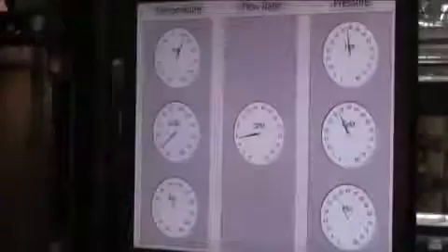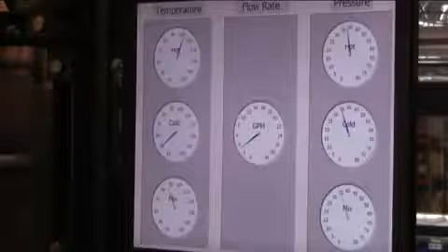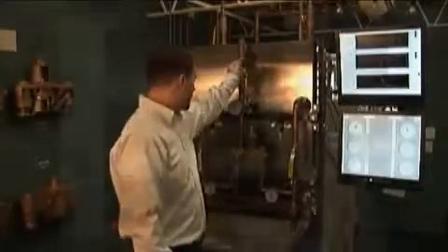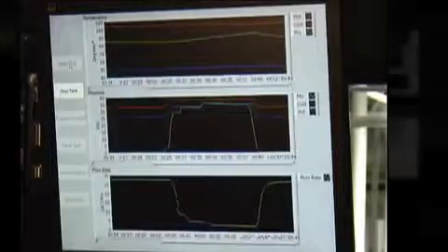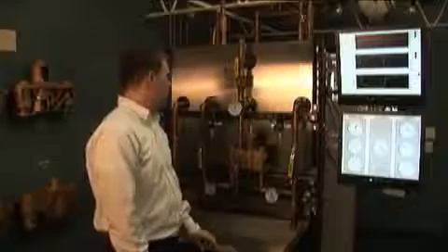But what if it were just an eye wash? I'll reduce it down to about what an eye wash would flow, and you can see we're still really holding temperature within a couple of degrees of that 85. Well, now what happens in an emergency valve if the hot or the cold are lost? This is really where it differs from a high-low thermostatic mixing valve.